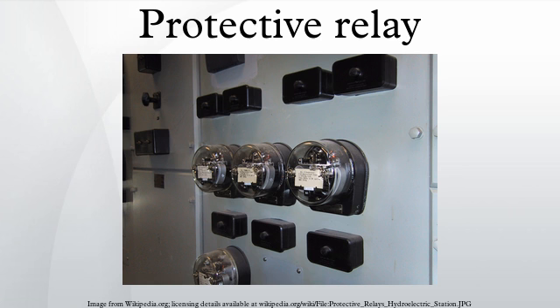An important transmission line or generator unit will have cubicles dedicated to protection, with many individual electromechanical devices, or one or two microprocessor relays. The theory and application of these protective devices is an important part of the education of an electrical engineer who specializes in power systems. The need to act quickly to protect circuits and equipment as well as the general public often requires protective relays to respond and trip a breaker within a few thousandths of a second. In these cases it is critical that the protective relays are properly maintained and regularly tested.